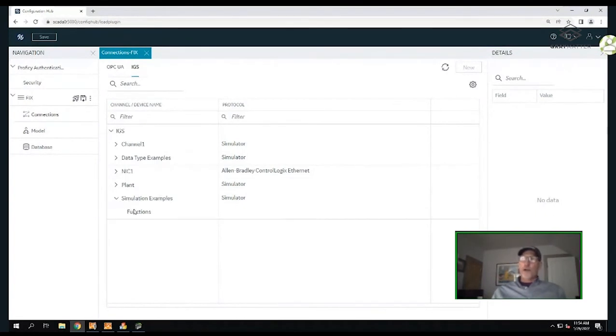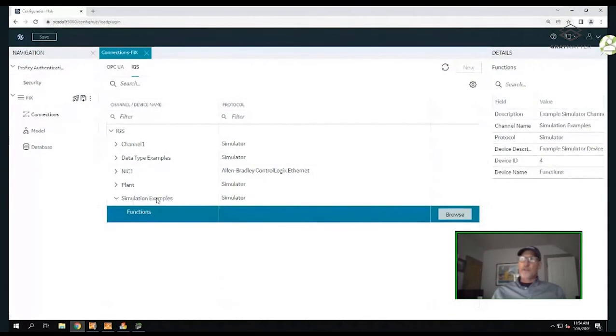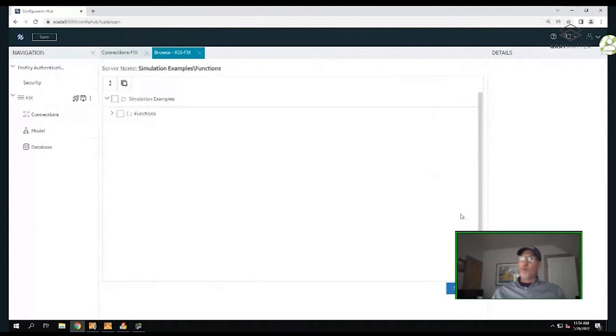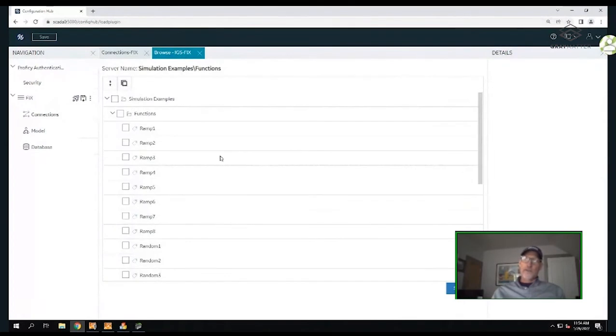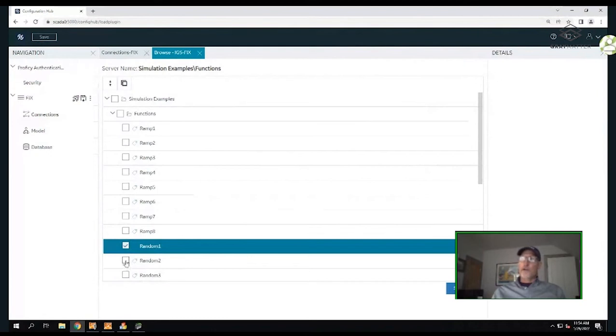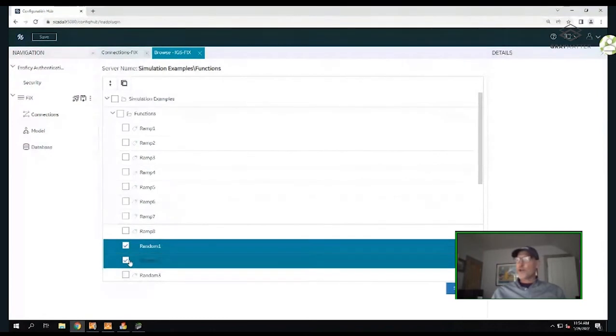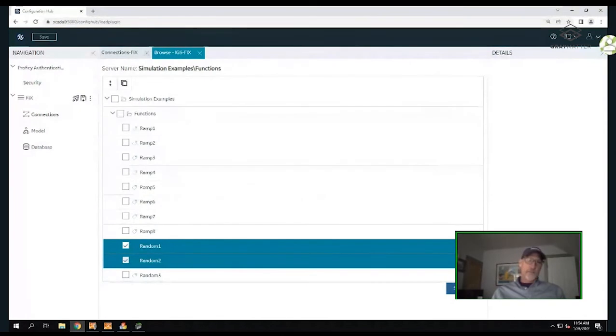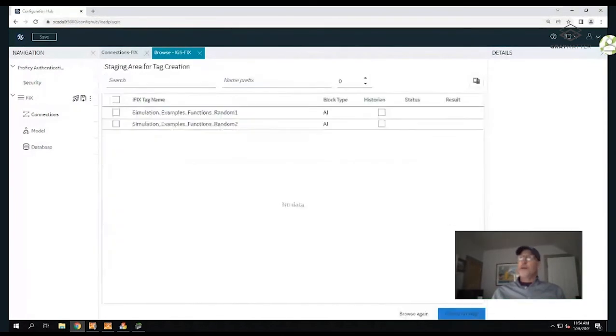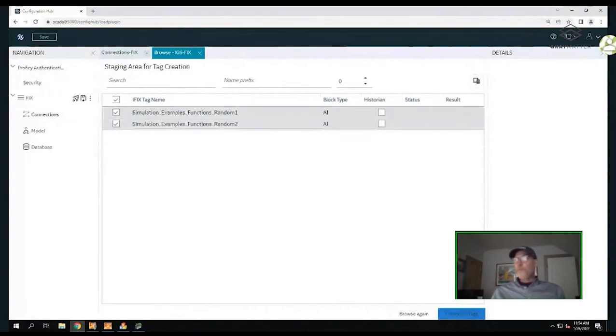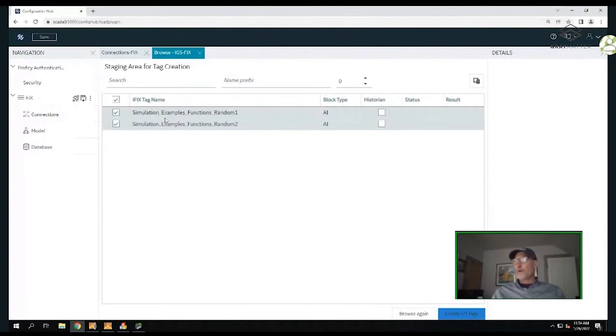I want to grab a couple of tags out of the driver. I'm drilling into my simulator tags and doing a simple browse, which gives me a list of all the tags in the IGS driver. This is a flat tag structure for this first example. I'll select two random tags, and they go into something called staging. The staging allows you to format your tag names.